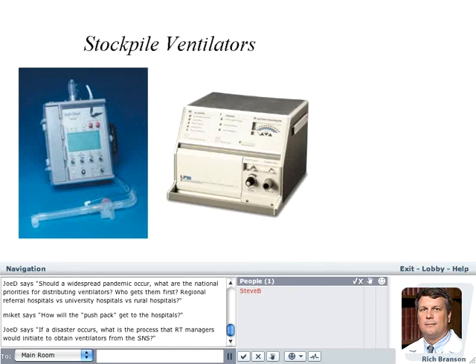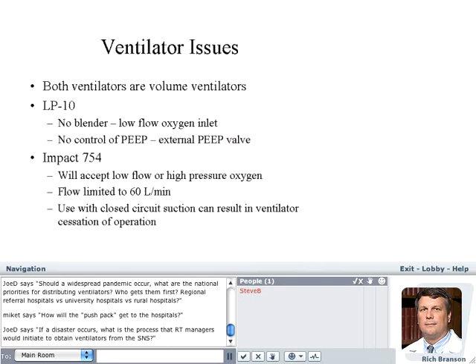So Eileen's already shown you the stockpile ventilators, so I want to tell you a little bit more about them. Both of them are volume ventilators. Neither one of them will do pressure control or pressure support. Now the LP10 is capable of setting a pressure limit, but it's a mechanical pop-off, so the ventilator still delivers the breath at the same flow rate and inspiratory time. The LP10 does not have a blender, so it will be difficult to give high FiO2s.